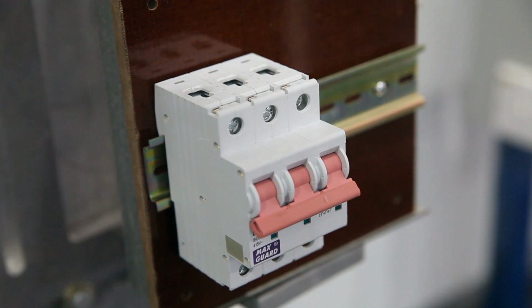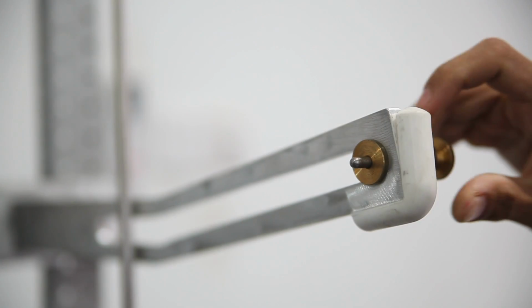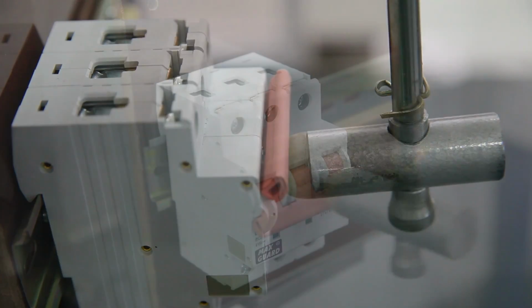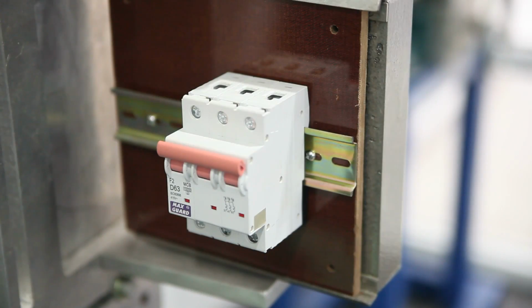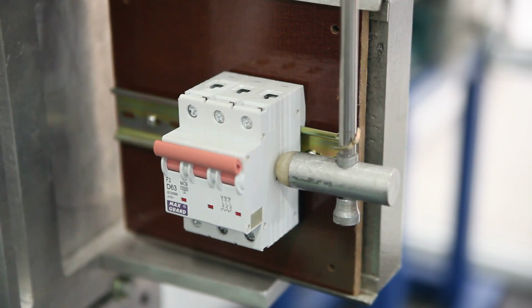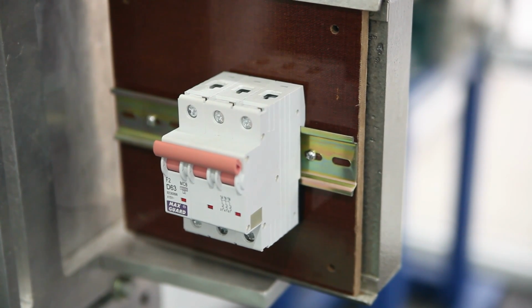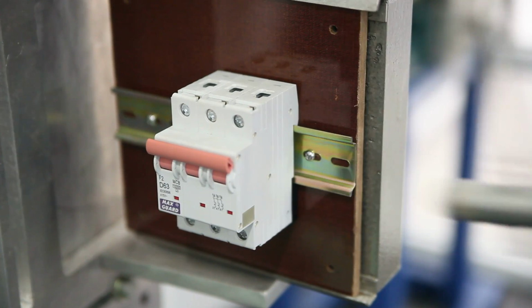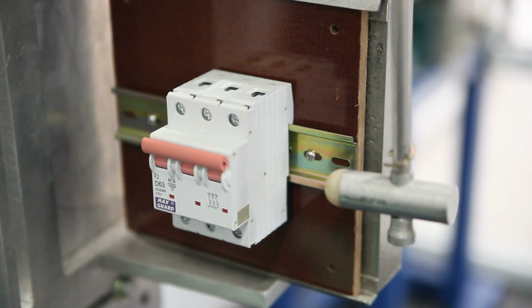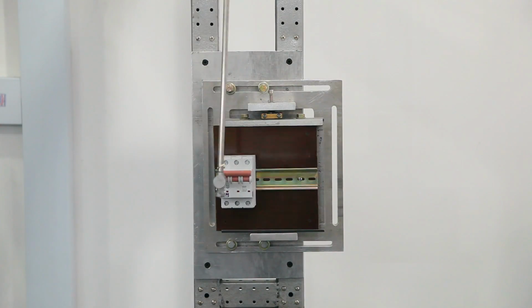2 impacts must be conducted on the MCB and RCCB on and off toggle, and the rest of 8 impacts are to be distributed evenly over the surface on both sides. At the end of the test, there should be no obvious visible cracks or breakages on the tested surfaces.